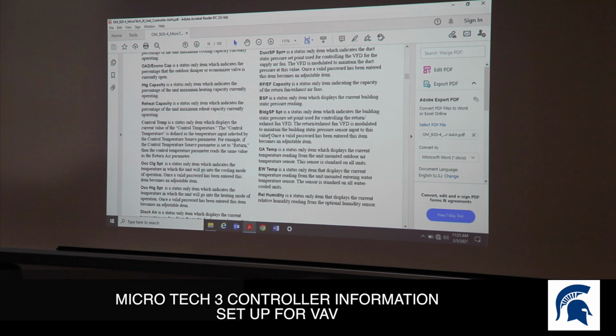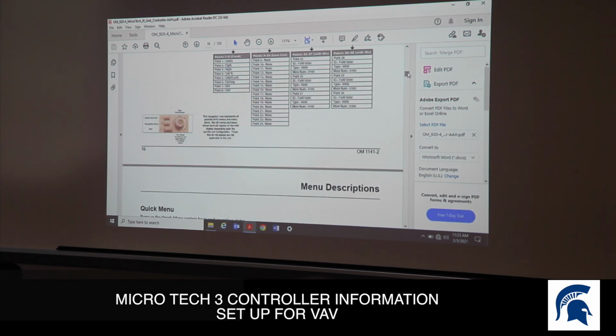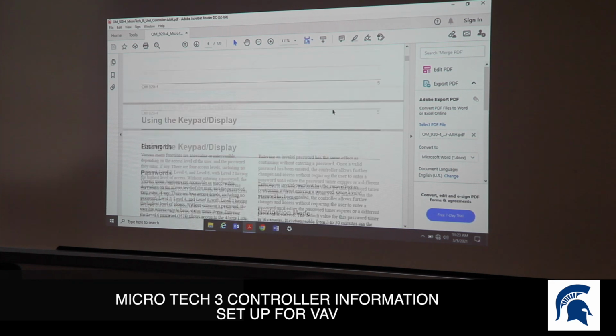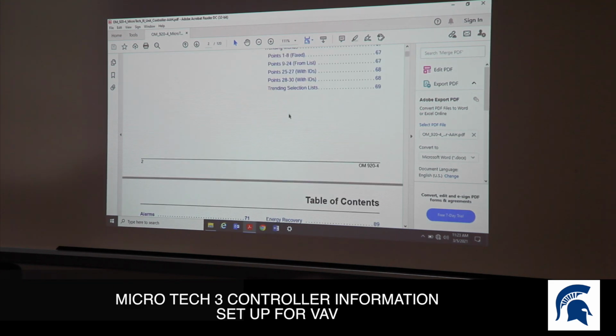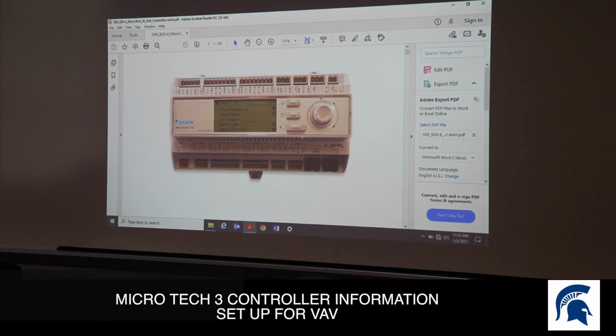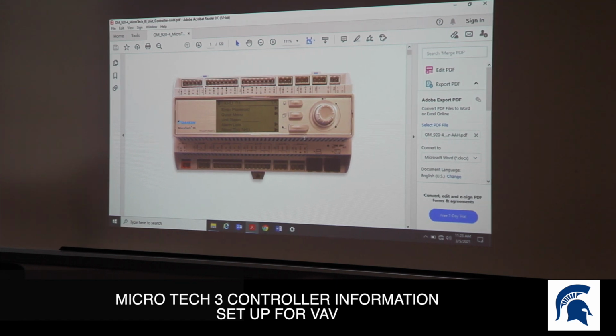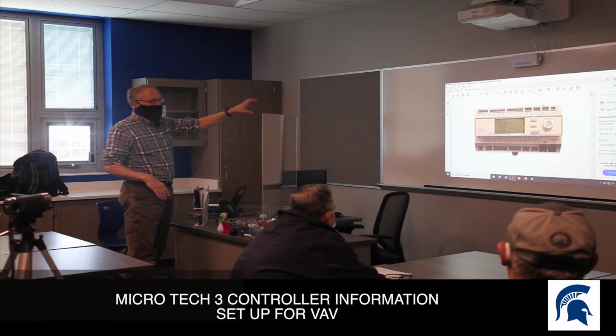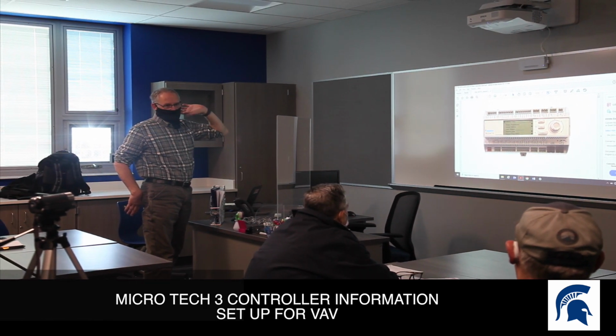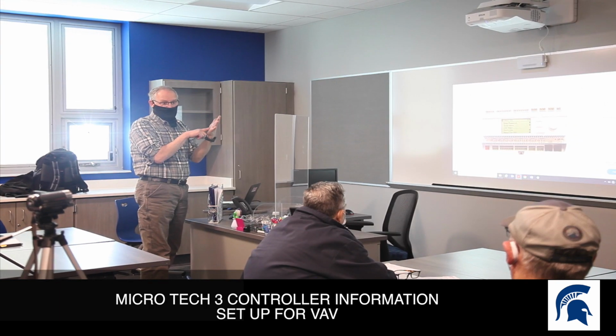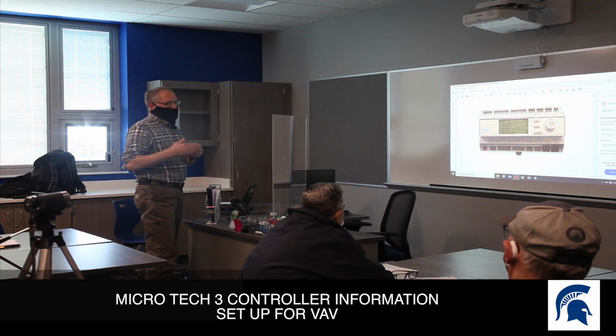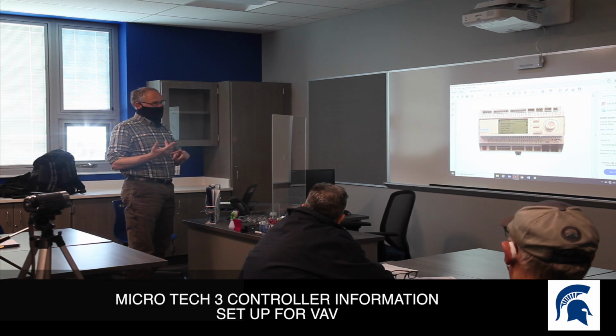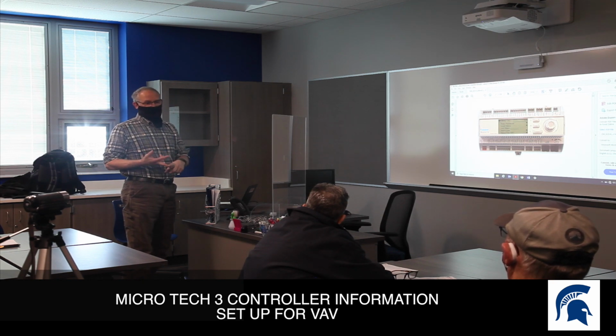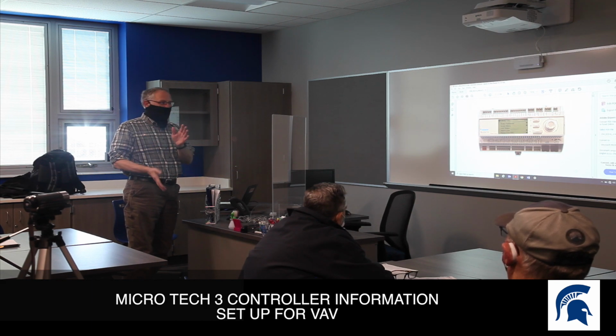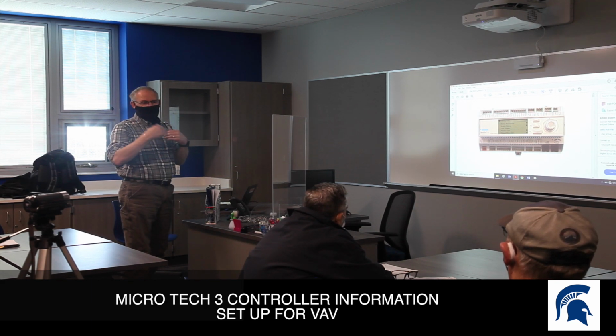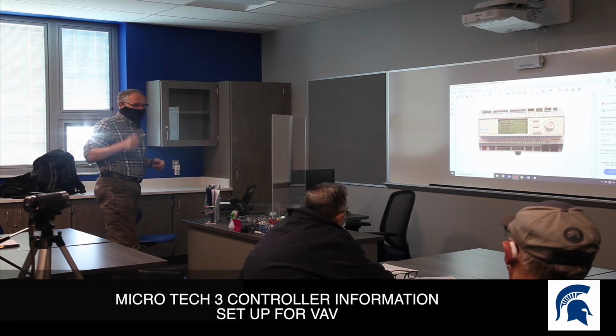I just wanted to give you an idea. As we go up there, you'll see what this looks like, and there will be modules tied to this. Everything on the left side is external communication, so there'll be a BACnet module on the left tied to your automation system. You'll know it's communicating because the light will be green. Everything on the right side is onboard communication for that machine, using modules for the expansion valves, condenser fans, and the valves that switch to hot gas reheat. All of those have to be green or it's not going to like it. We'll watch how that happens upstairs.